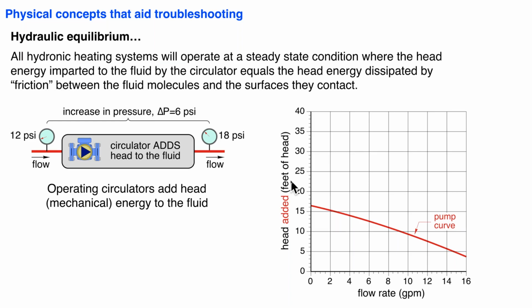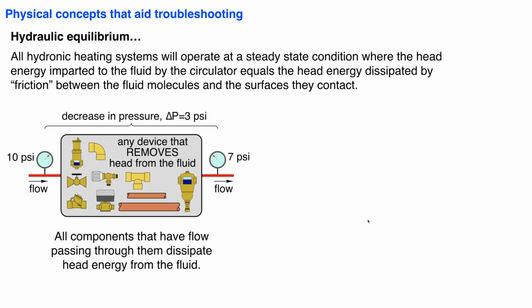But one of the practical ways to think about this is the number of foot-pounds of mechanical energy added to each pound of fluid as it's passing through. And you can see it's definitely not a constant. The higher the flow rate, the lower the number of foot-pounds of mechanical energy added to each pound of fluid. So that's the energy input side. Now let's look at the energy dissipation side. Everything that the fluid moves through, fittings, pipes, air separators, dirt separators, valves, everything that there's actually motion of fluid passing through causes dissipation of head energy.